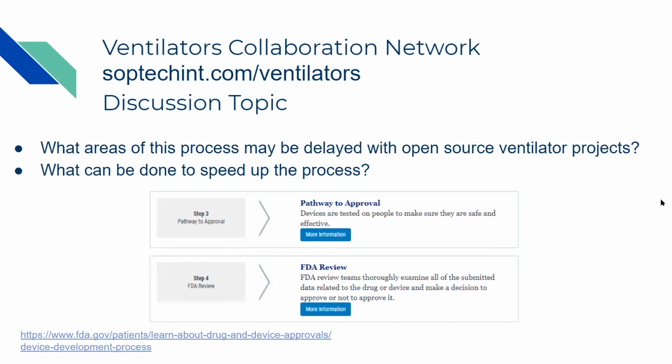Now, FDA, I'm not sure. I'm just putting it out there. So it might be good to always look into it. It's not unlike UL. FDA has maybe a 3rd and 4th process when they're looking at devices like these. But it might be good to keep that in mind, so that if you're facing an 8-week delay at the moment to get an approval, there might be some tricks that we can use. It costs double because now you're sending 2 units, but at least you get to the end result quicker than usual.